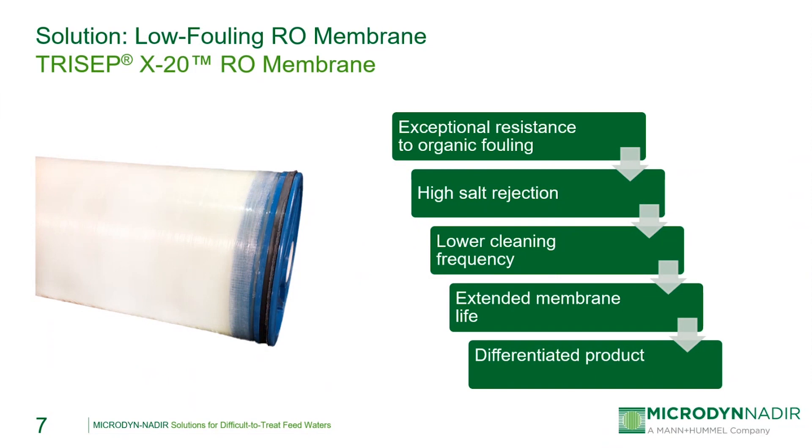MicroDyn-Nadir offers the TRISEP X-20 low fouling RO membrane for situations where the RO feed has high fouling tendencies. The membrane chemistry itself is different from standard polyamide membrane chemistry, giving the membrane surface a more neutral surface charge throughout its operating pH ranges, which makes foulants significantly less likely to adhere to the membrane surface compared to the negatively charged surface of a standard polyamide RO membrane. The membrane exhibits high salt rejection in combination with its increased organic fouling resistance, leading to a lower frequency of cleanings and extended membrane life.